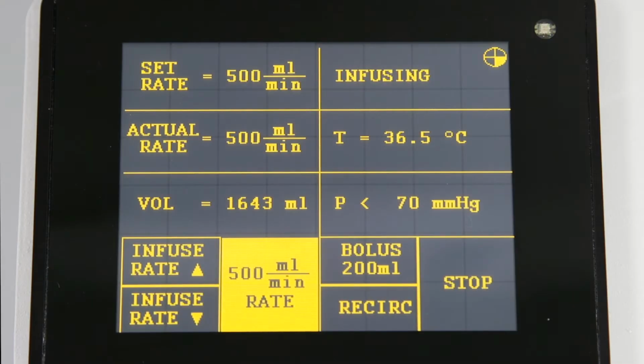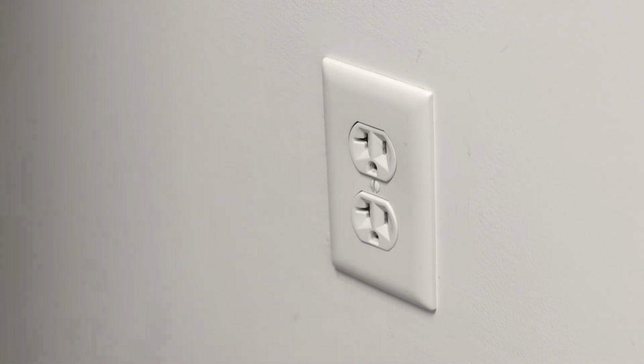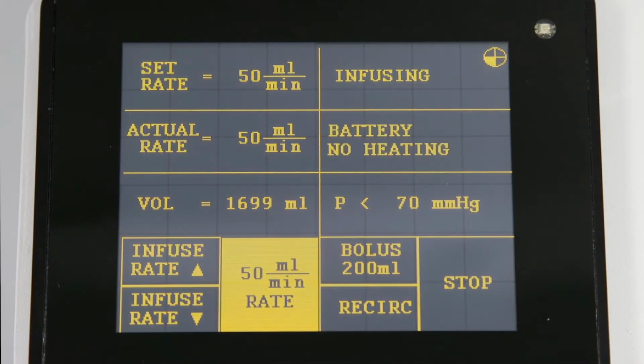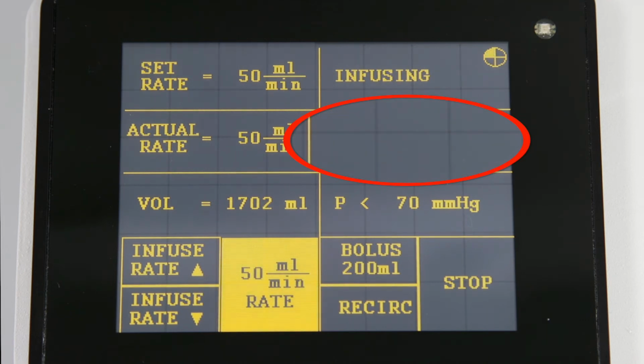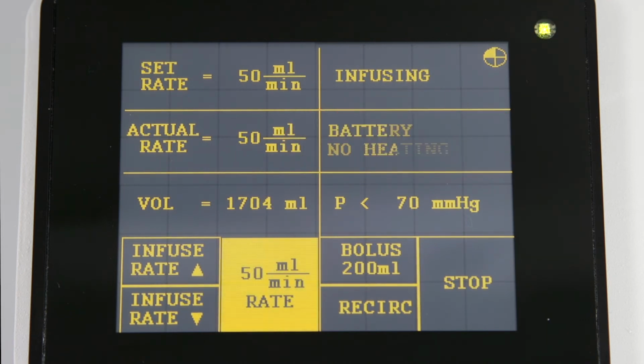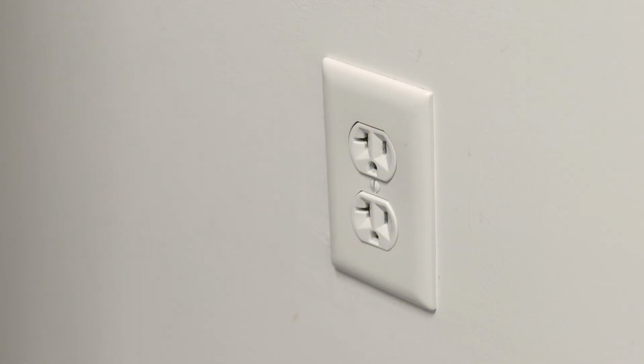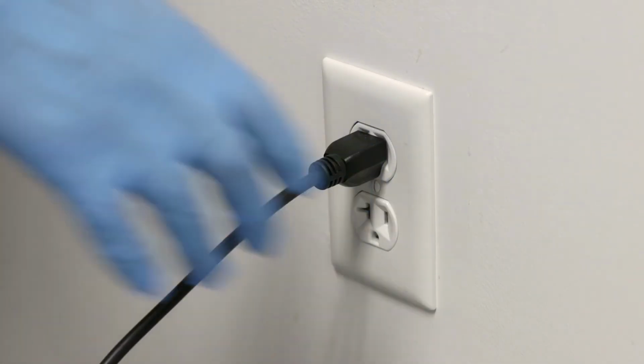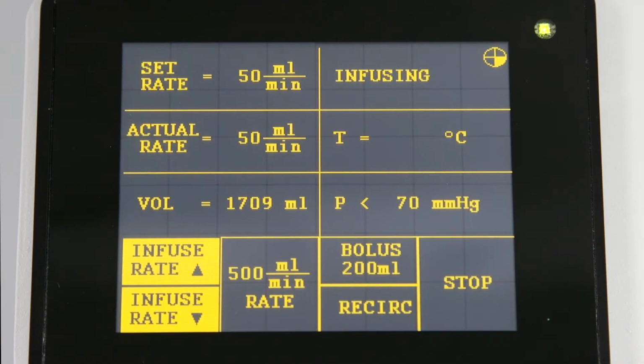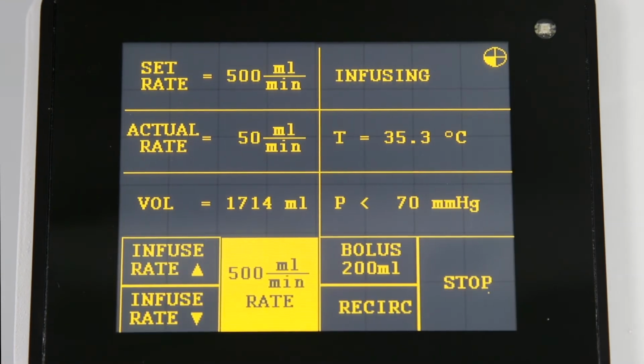If there is a loss of power, if the machine is accidentally unplugged, or if the patient needs to be transported between units, the Belmont Rapid Infuser RI-2 will automatically switch to battery power. There is no fluid heating when the device is on battery power. To protect the patient from rapid infusion of cold fluids, the flow rate is limited to a maximum of 50 milliliters per minute. Plug the device back into a dedicated circuit as soon as possible to reinitiate warming and adjust to a higher flow rate if needed.